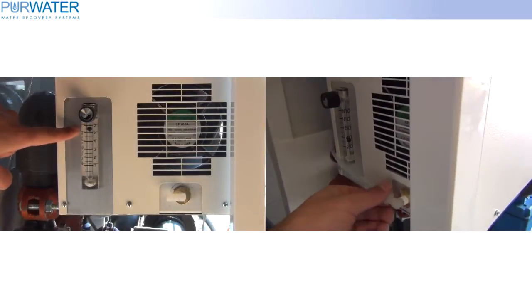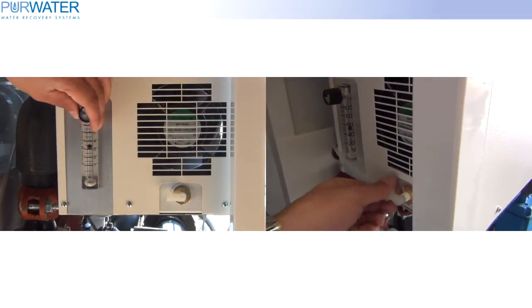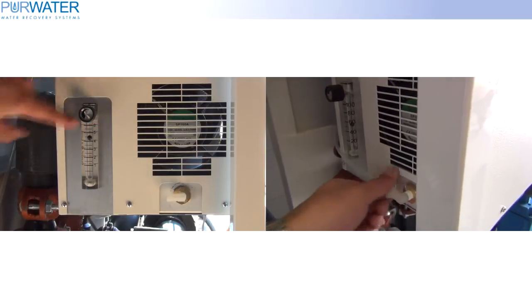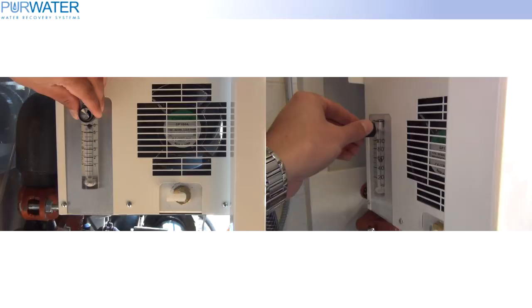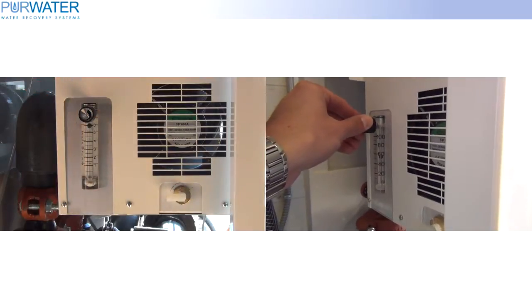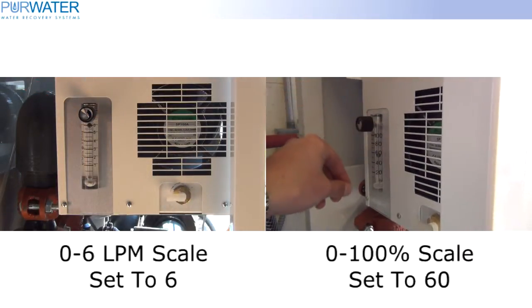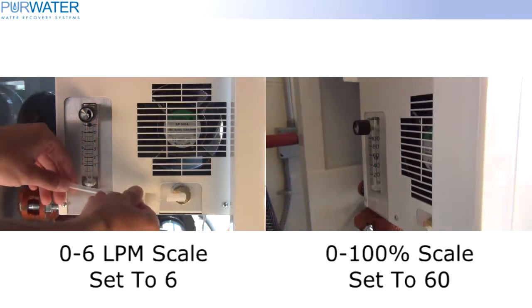On the left side of the machine, with the tube disconnected, the flow meter ball should be set at 6. If you have a unit that has a scale of 0 to 100, the ball should be set to 60.